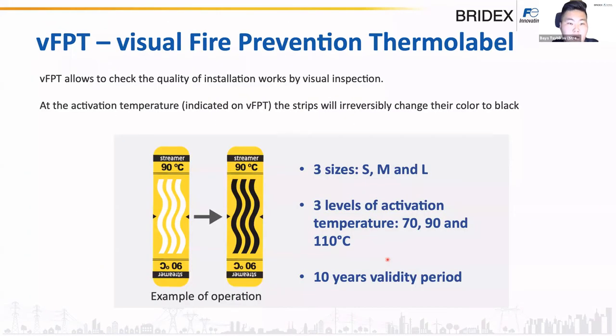Also, we have an auxiliary product, which is the VFPT, or Visual Fire Prevention Thermal Label. These small stickers are needed for visual inspections. They don't have any gas inside. It's just the same material as the round dots on the RFPT. As soon as the sticker is heated up to its activation temperature, let's say 90 degrees, these white strips turn black irreversibly. So you can stick it everywhere inside the electrical panel, check in 1-2 weeks, and see which stickers turned black. That will give you a clear understanding of which connections are not tight or are degraded. Like our stickers with gas, it has a 10-year validity period, or lifespan. And we have different sizes and activation temperatures in the product range.